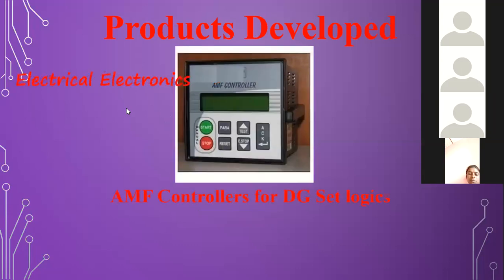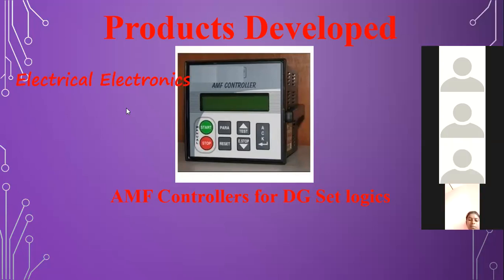Now coming to this standalone system, the AMF controller. AMF is automatic changeover against mains failure for generators, DG set, diesel generator set. It gives power to the load, and when power fails, it switches off the mains and starts the engine, puts the load onto the generator, and runs it till power is retrieved. This type of thing is achieved using the AMF controller.